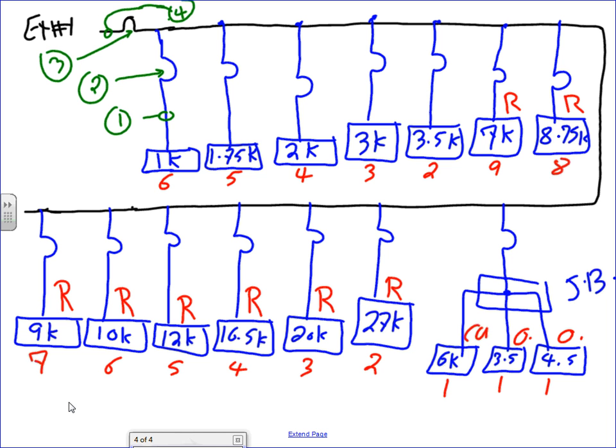Any questions, guys? The last one here, I threw that one in for the example, guys. It tells you I decided to be lazy, to pull one branch circuit, tap the branch circuit in a J box, and feed 2 ovens, the O's are for oven, and 1 cooking unit. Remember that little exception, that note number, what was it? Number 4 or 5? Cool. So let's go and size this.